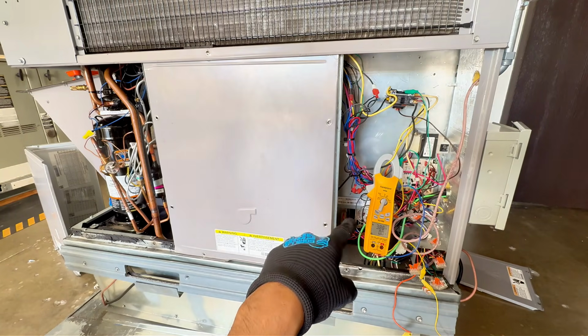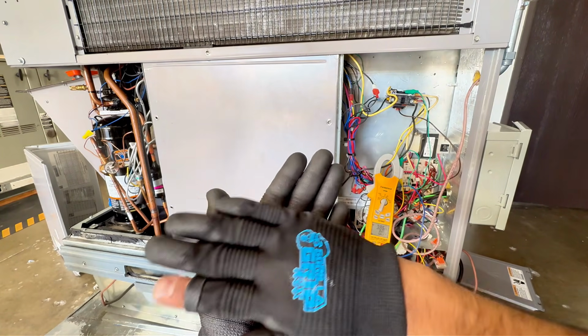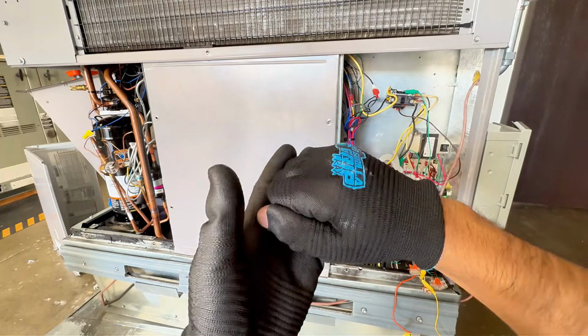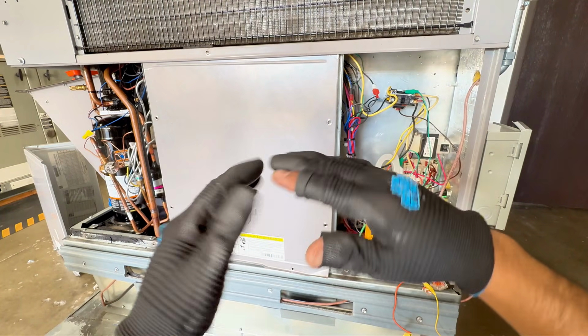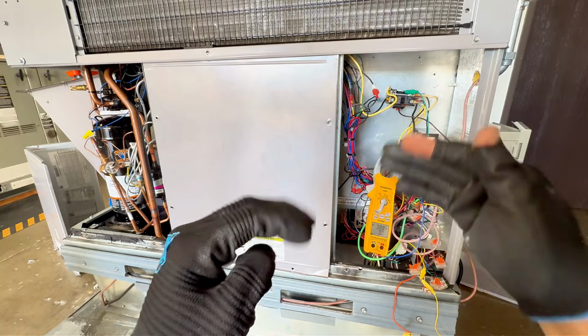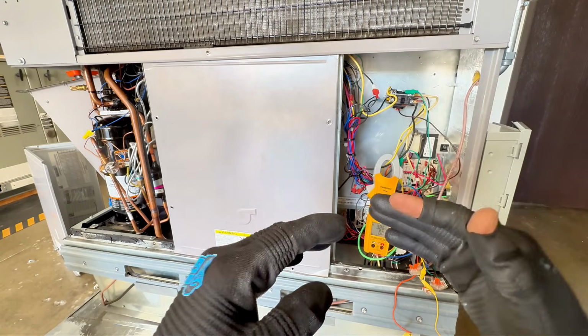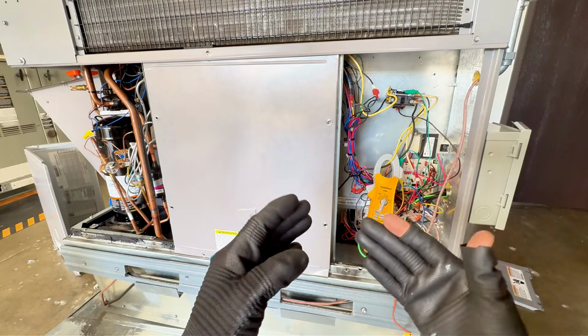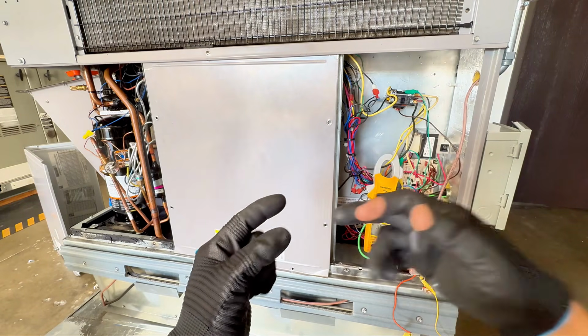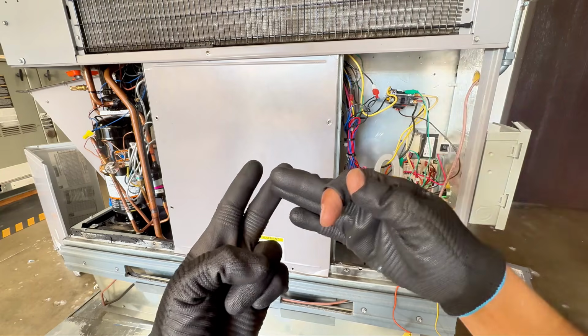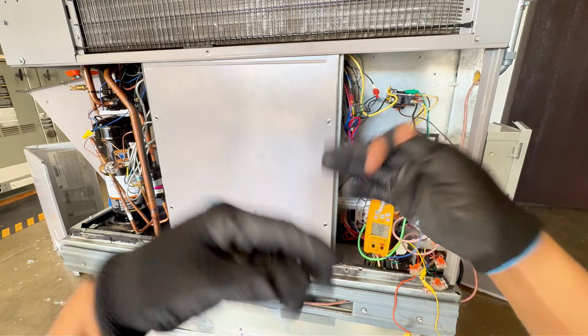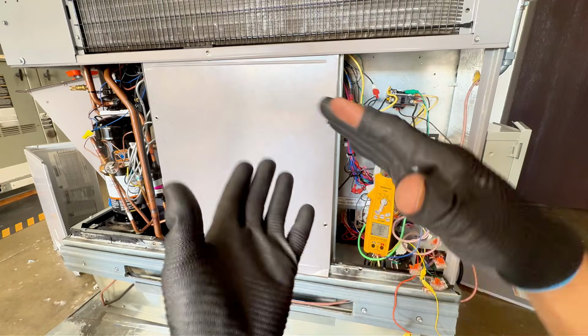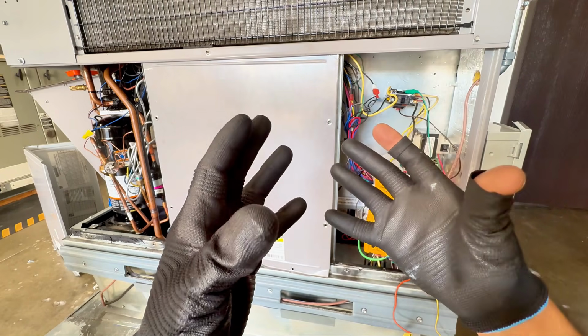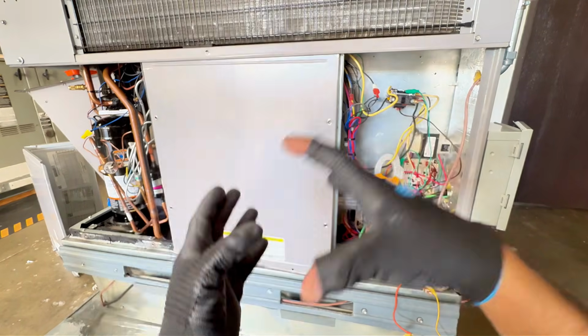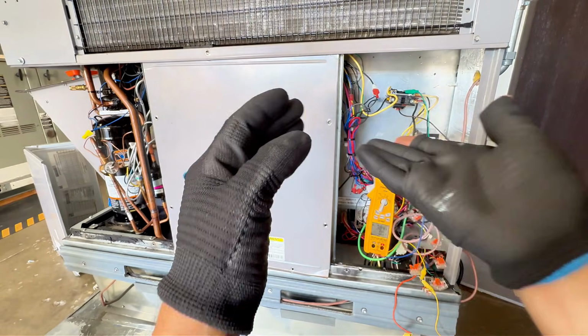Now, the only way it would pull less is if you have a complete blockage, a collapsed duct. I've seen those. When it's a complete blockage, then the amp draw goes down. But think about it, in most cases, that doesn't really happen. In most cases, it's undersized return ducts, no maintenance, dirty filters. So it's going to make up for it because there's a restriction, not a complete one, but there is a restriction. And that's going to be the most common one. With a slight or somewhat of a restriction, it's going to pull more current, more amps, to make up for it.